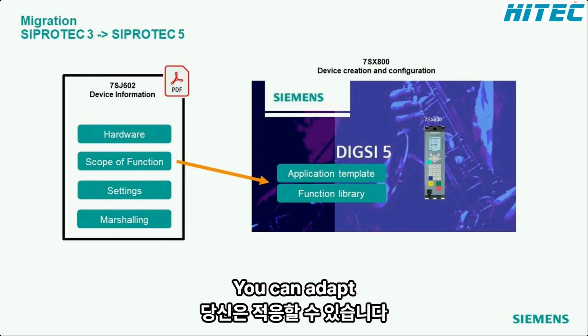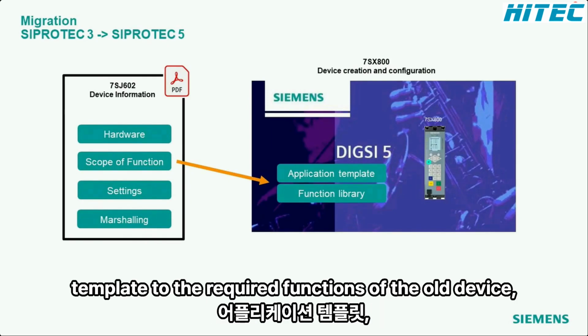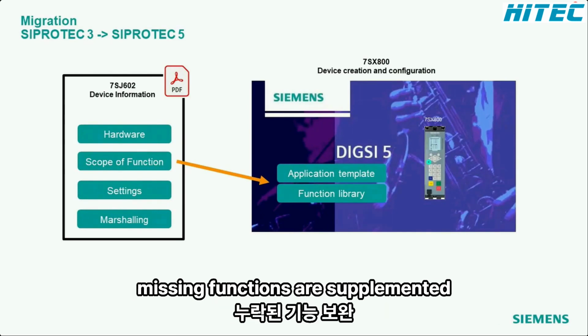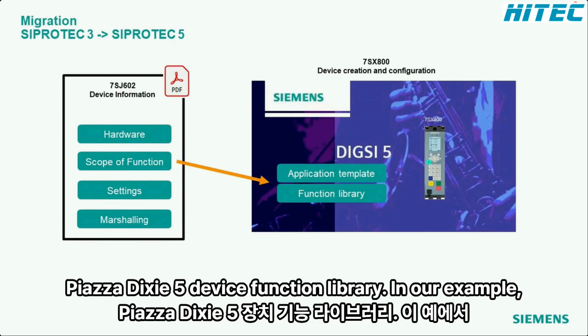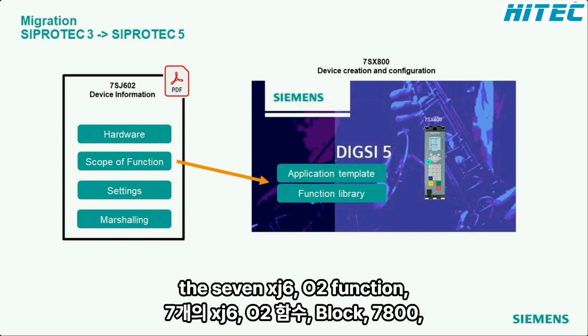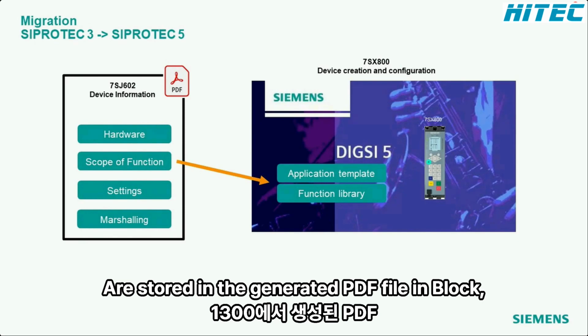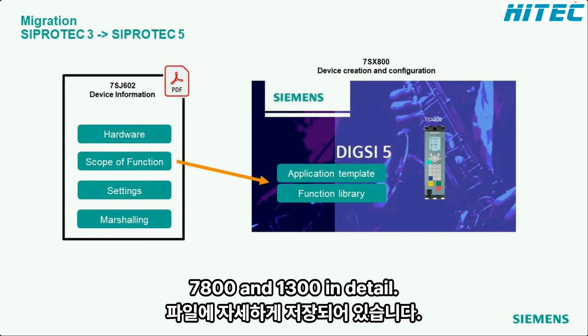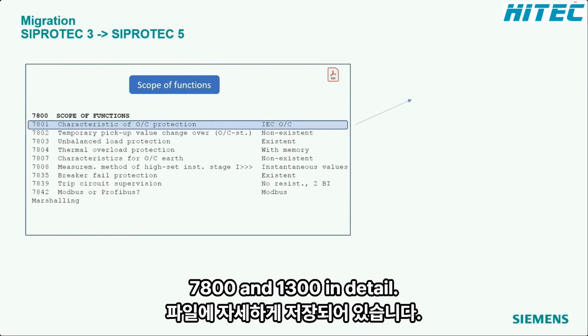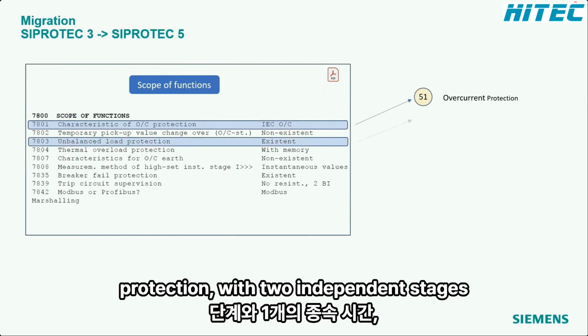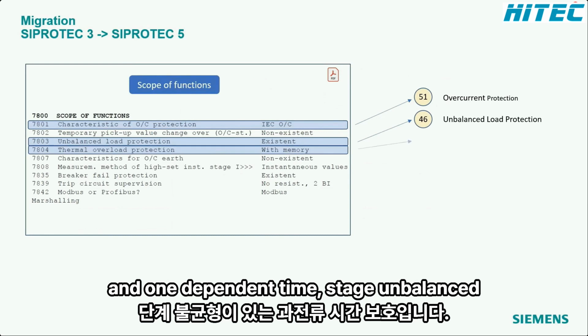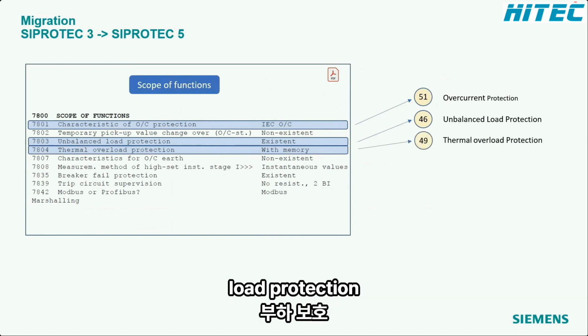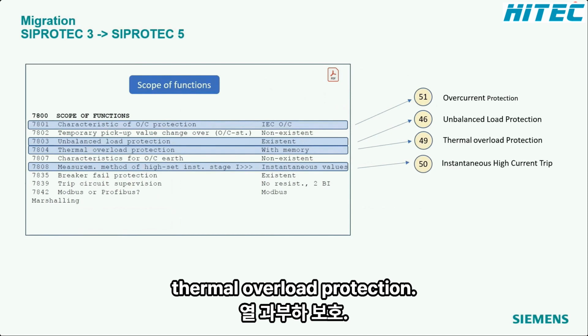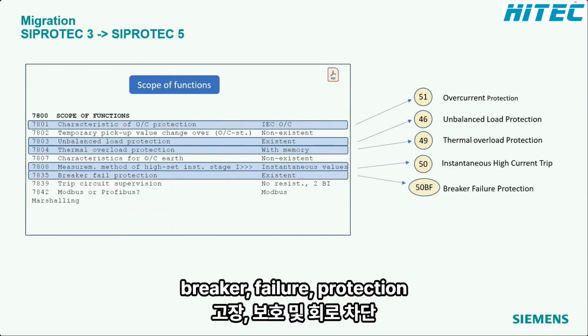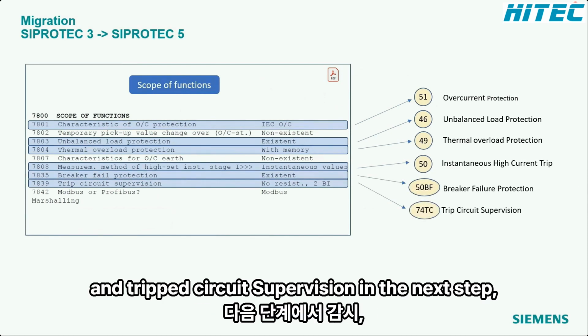With DIGSI 5 you can adapt an application template to the required functions of the old device. Missing functions are supplemented via the DIGSI 5 device function library. In our example, the 7SJ602 functions are stored in the generated PDF file in blocks 7800 and 1300. In detail, these are overcurrent time protection with 2 independent stages and 1 dependent time stage, unbalanced load protection, thermal overload protection, instantaneous high current protection, breaker failure protection, and trip circuit supervision.